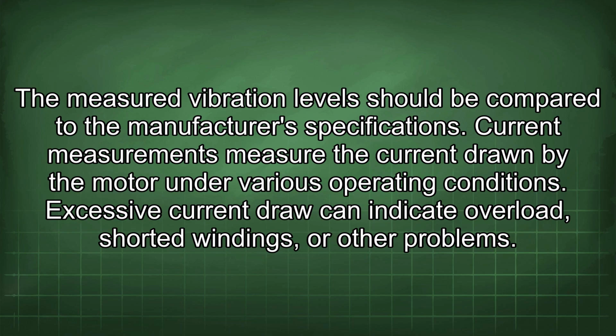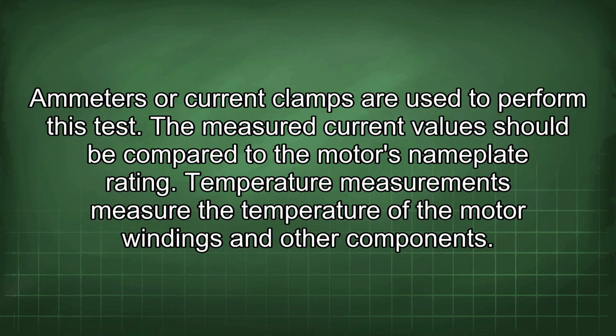Current measurements measure the current drawn by the motor under various operating conditions. Excessive current draw can indicate overload, shorted windings, or other problems. Ammeters or current clamps are used to perform this test. The measured current value should be compared to the motor's nameplate rating.